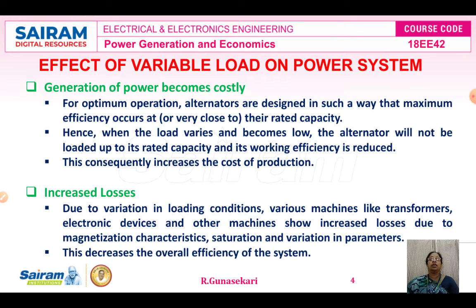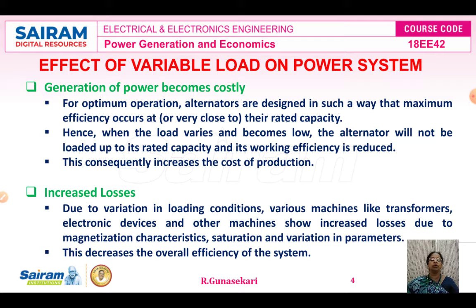Now we studied about the effect of variable load on the power system. Because the load can vary — with respect to time only, it is not constant throughout the day. The first effect is that the generation of power becomes costly. For optimum operation, the alternator is used to generate power. The alternators are designed so that maximum efficiency occurs at their rated capacity. If the load becomes low, the generator will not be loaded to its rated capacity, its working efficiency is reduced, and this consequently increases the cost of production.